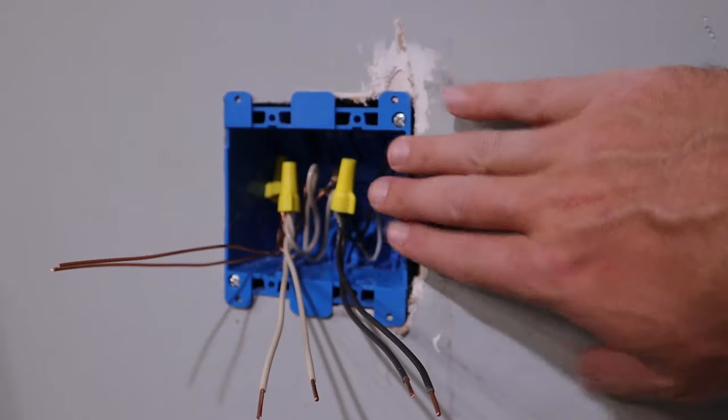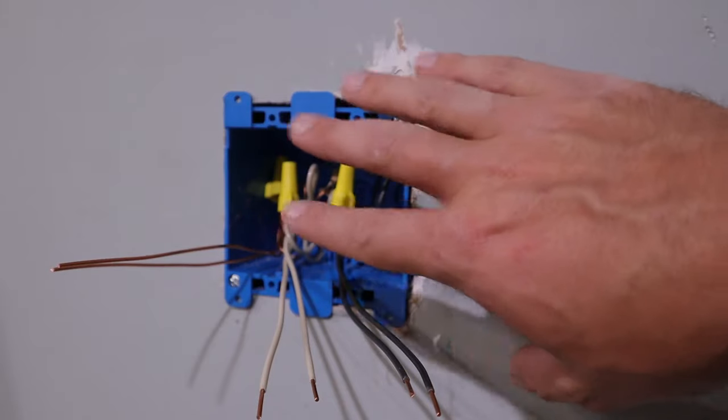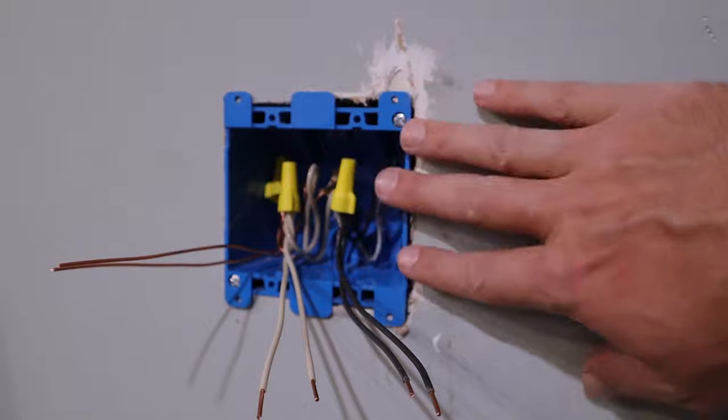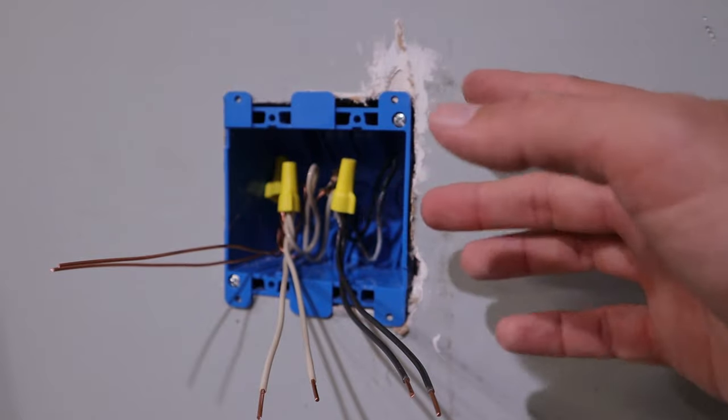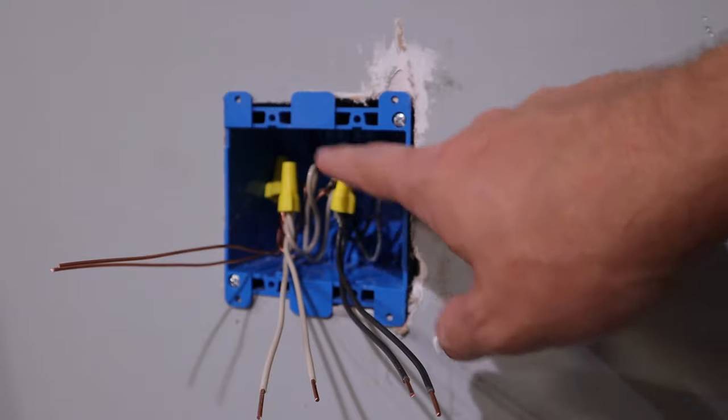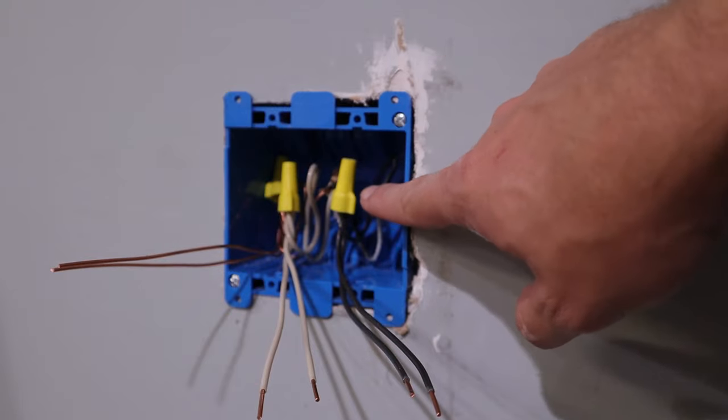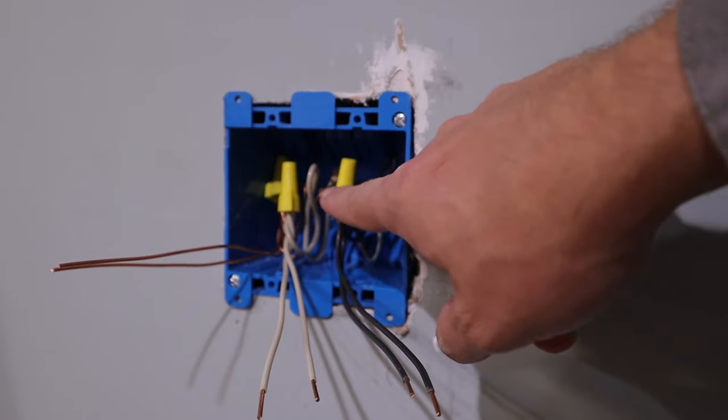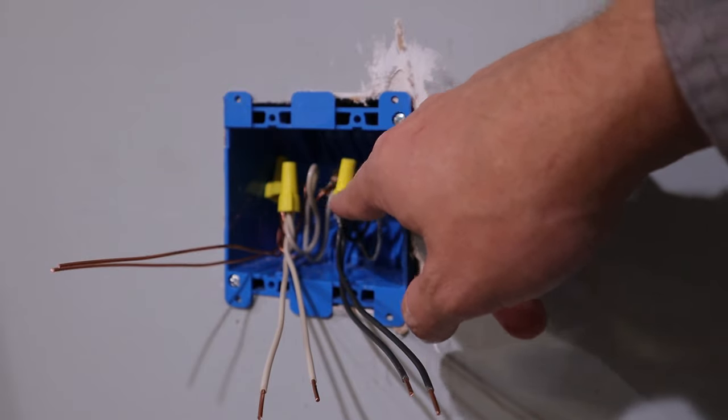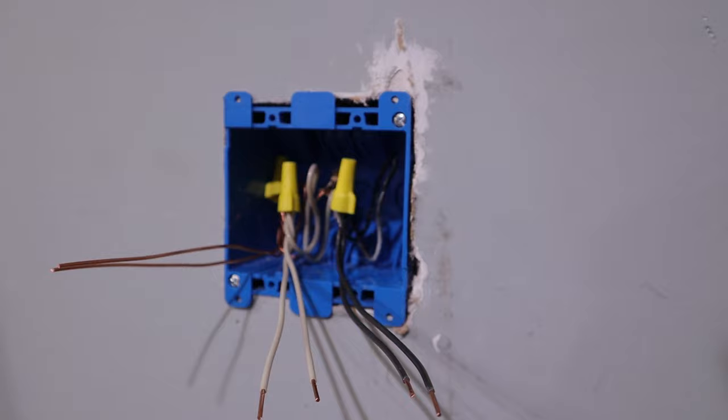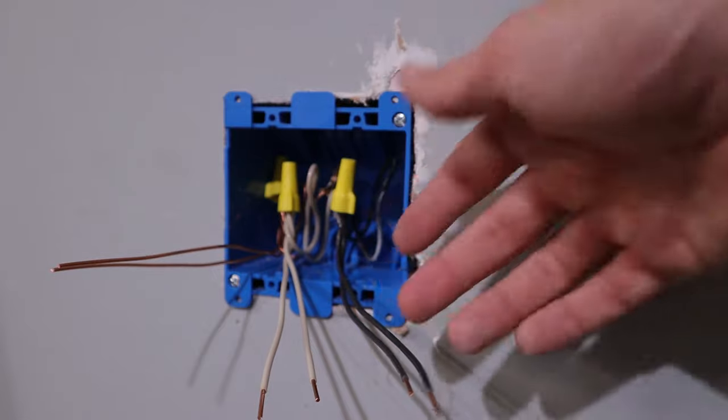Now something to note, this outlet box just so happens to be at the end of the run for the outlets, so there's not going to be any power that's going on to another box. If there was, there would have been an additional wire, the wire that's going on to the next outlets, that we would have also had to have put each color underneath each of the wiring nut. So instead of there being three underneath of each, there would have been four.